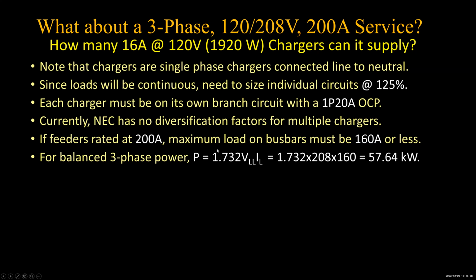And we're going to divide that amongst these 1.92 kilowatt chargers. So 57.64 divided by 1.92, or 57,640 divided by 1920 if we're all in watts. That says we can have 30 chargers plugged into this without any kind of diversification at all. It's just a three-phase 120/208 service with level 1 chargers, and that'll run 30 circuits. The 30 chargers. And if each of those circuits can have more than one charger on it because the chargers talk to each other, then maybe we're up to 90 or 100, something like that.